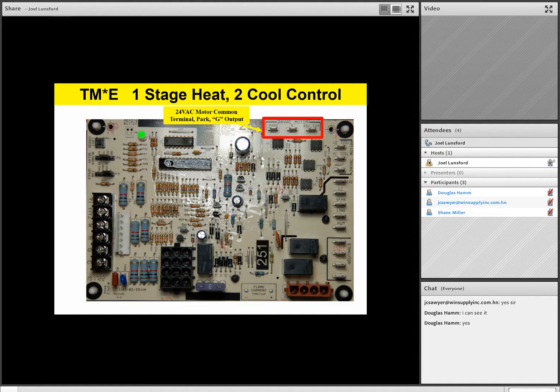Then you have a G terminal. Maybe back up for a second. You have a G terminal that would be the selected speed tap for a G only call. And then you also have a 24-volt common, where it says 24-volt motor, in that little area I have highlighted. Now as we move down the right side of the board, we have different speed tap selections: low cool speed, high cool speed, and heating speed.